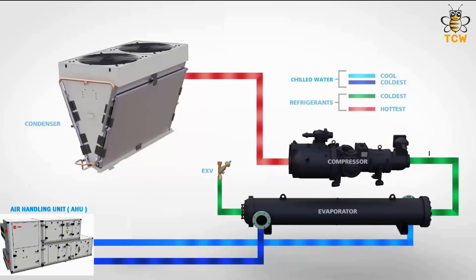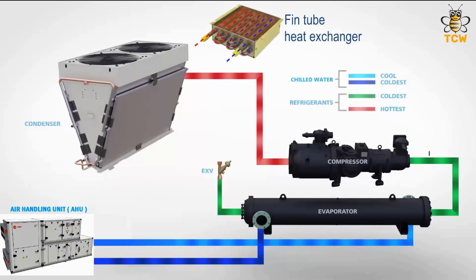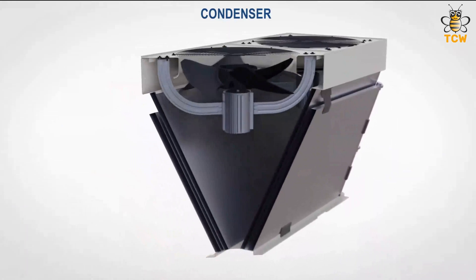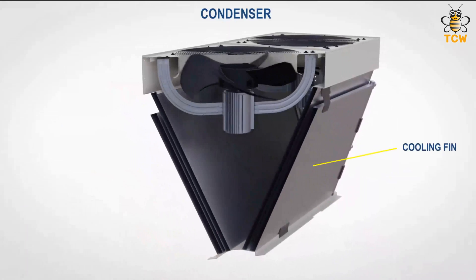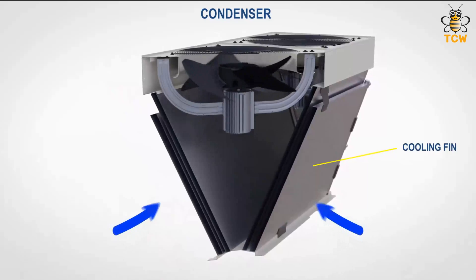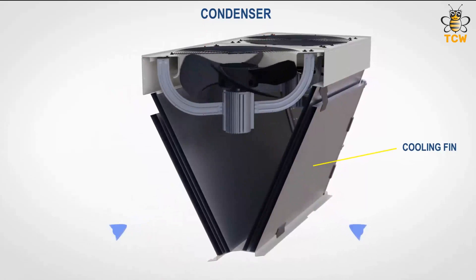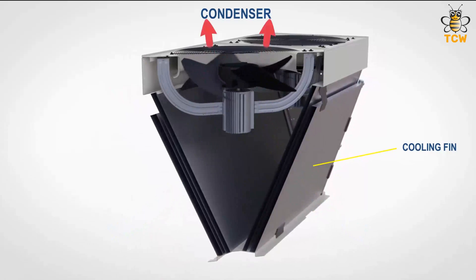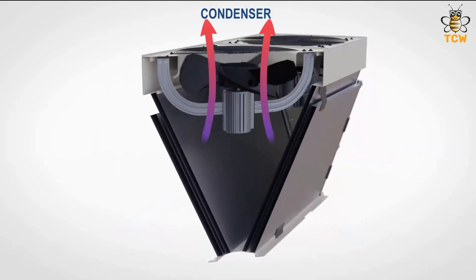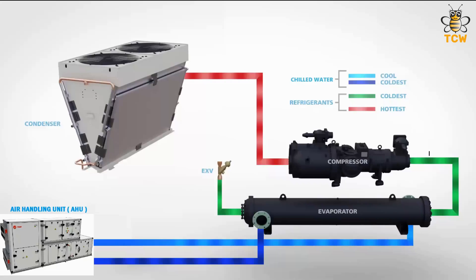This hot refrigerant vapor is blown into the condenser. In the condenser, the high temperature refrigerant vapor is passed through a thin tube heat exchanger. When the high temperature refrigerant vapor flows inside the tubing, the fan sucks air in the inner cavity, causing air to flow through the cooling fins. The air passing through the cooling fins will absorb the heat from the refrigerant vapor, making the temperature of the refrigerant vapor drop.